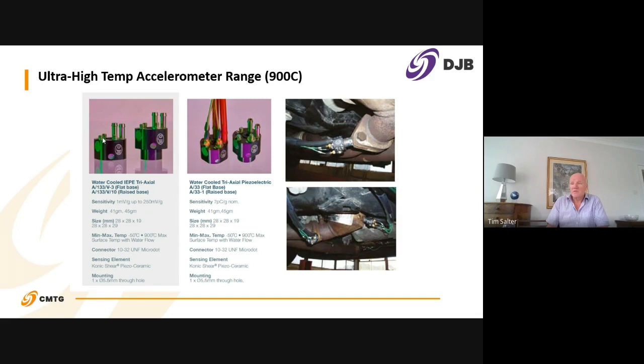There's also two versions of this. You can see one here with a flat base and one which has got an extended base. That's to allow customers to mill a radius onto there. If you want to fit this sensor onto a curved manifold where you need to get the coupling good to the surface, then a flat surface naturally won't give you good coupling onto something like a tube. So the radius of the test item can be milled onto here, or the profile of it can be milled onto here.